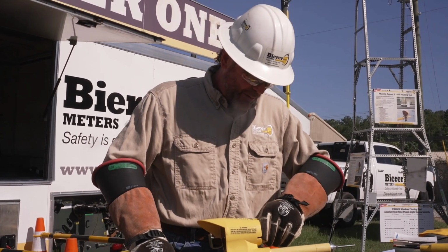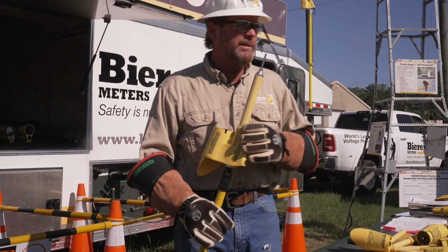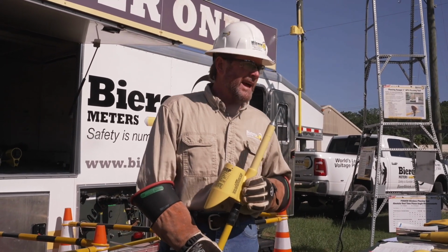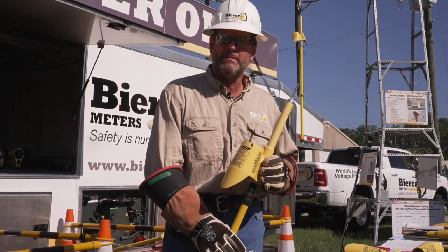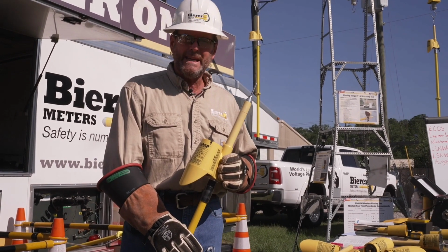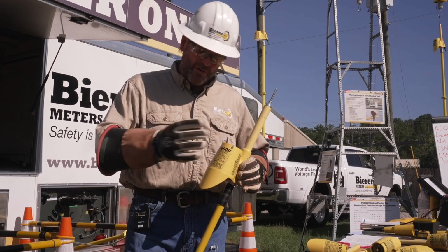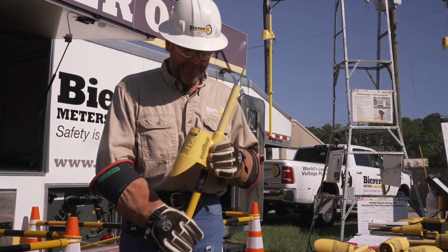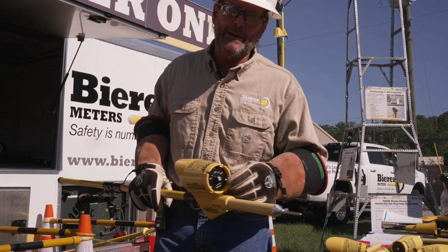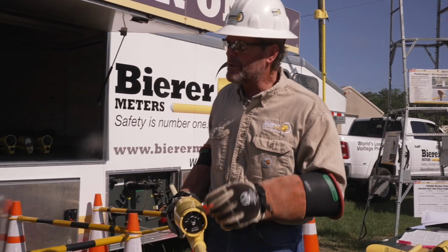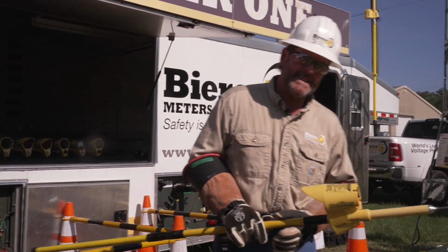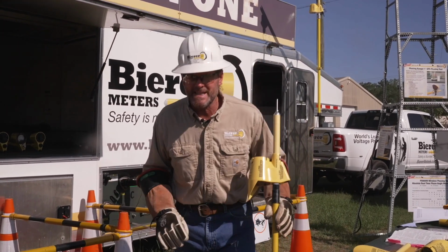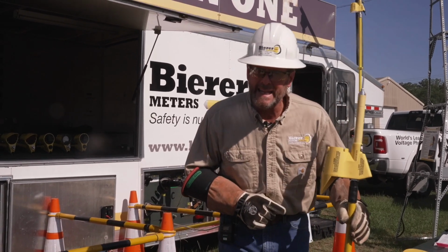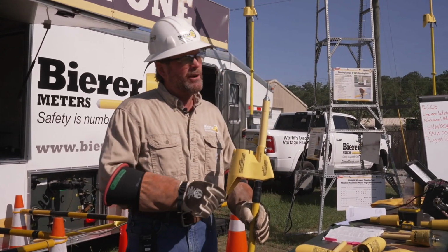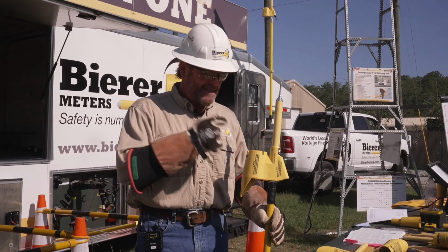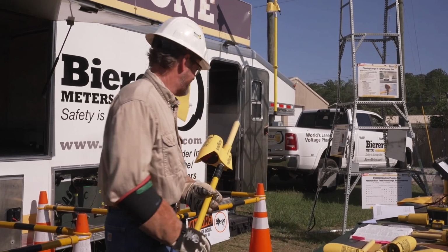It's very sensitive. But we're going to use it, say we got a storm, it's dark outside, and we're not sure exactly where that conductor is, lots of bushes around, can't see very well. So we'll put it in the P setting to navigate through those shrubberies, through the darkness, you might say. Then we're just going to simply approach, you see the P setting, our capacitive test points. If you don't have capacitive test points, you can put the tool in the P setting and go to the base of the elbow, and there's that semicon material this tool will sniff out. Let's show you.